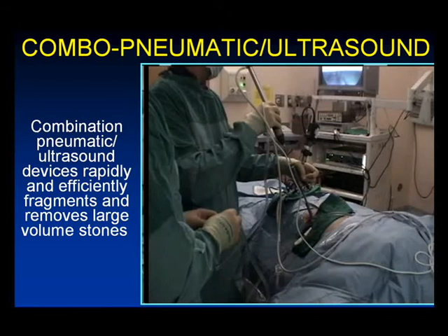The ultrasound probe. We had that problem initially, and basically what happened was the ultrasound was actually too powerful. And so what we found, they've done some software modifications, but also we now only keep the ultrasound power at about 70%. And by turning down the ultrasound, it's actually worked quite well for us over the past, say, 6 months. So your experience was not unique. So we had about 4 that come in. Well, we have the Olympus as well, and this one now has been working well for the past 6 months. So I've been very pleased.